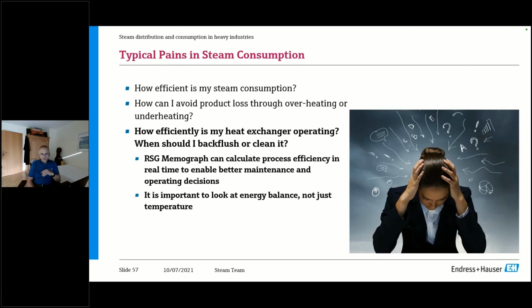So how efficiently is your heat exchanger operating? When should you clean it? Using the memograph, you can really monitor the efficiency of your heat exchanger. You can check the energy in versus energy out over time. And in case something is wrong, you will see a drift in that value. And then using that balance, I would not only use temperature. I would use the true energy. The measurements are there and they are offering you a better solution, a better measurement to know when it's time to clean your heat exchanger.